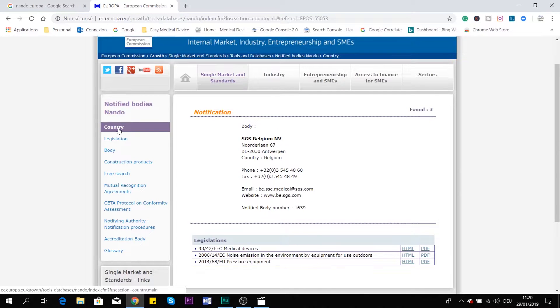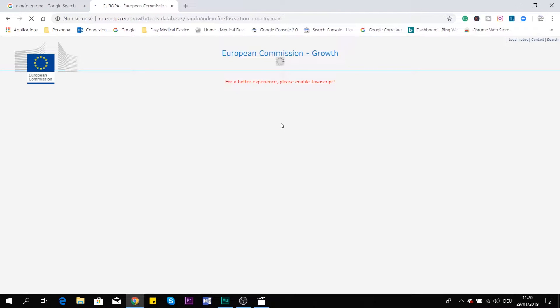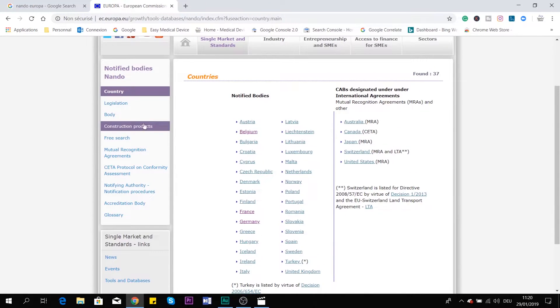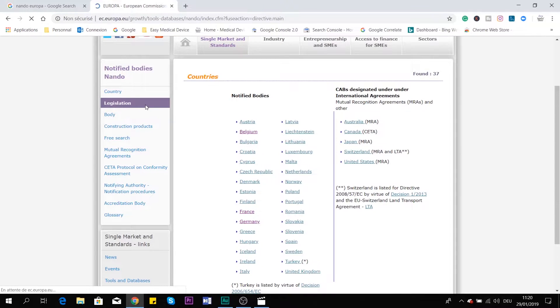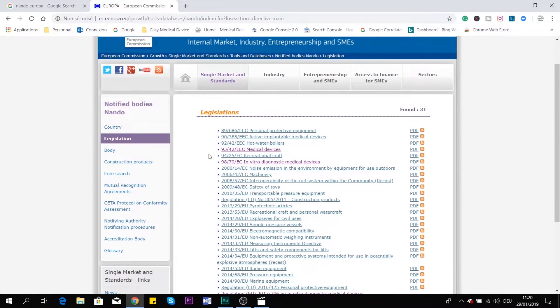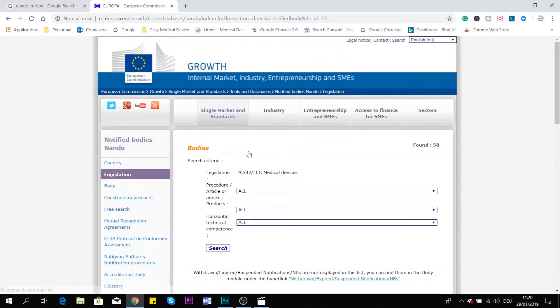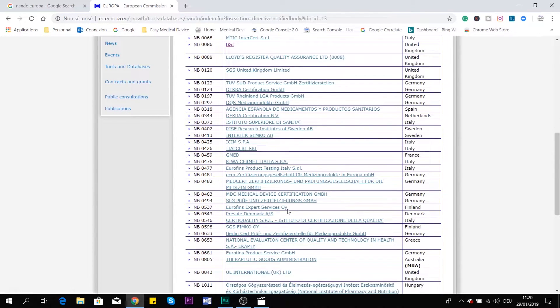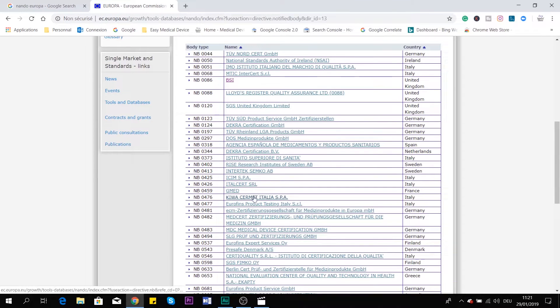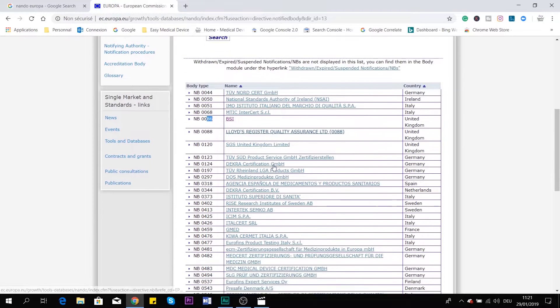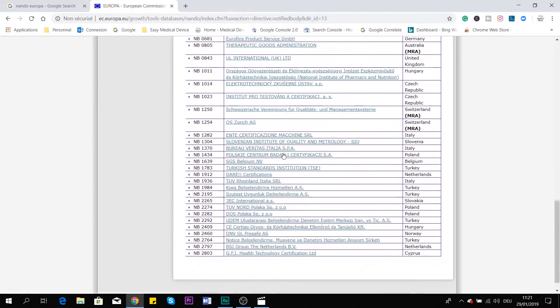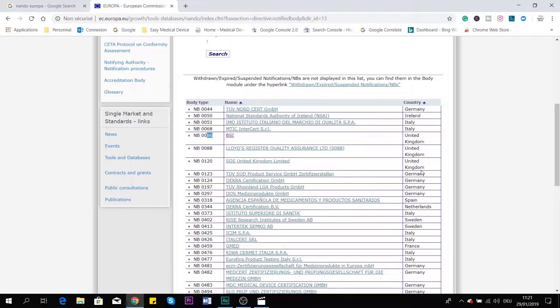Now that we've seen the country view, where you can check all the notified bodies in your specific country, we can go to the legislation view. Legislation will show you notified bodies per legislation, not by country. If we go to the Medical Device Directive 93/42/EEC, here you see all the notified bodies that are specifically for medical devices — for example, GMED in France with number 459, and BSI with number 86. You can also see the countries where they are located.